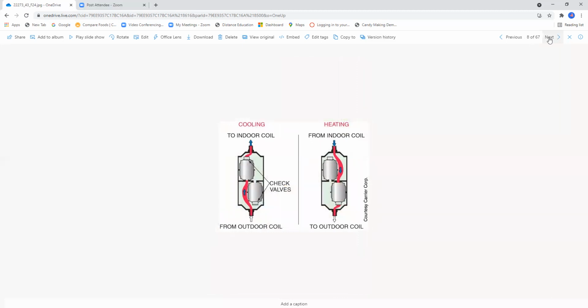Okay, here we have the check valves, basically on the cooling to the indoor coil. So basically, if we have refrigerant going from the outdoor coil, notice that it bypasses this one valve, goes directly through this check valve to the indoor coil. Now we go from the indoor coil, and notice we bypass this check valve, and then we go to the outdoor coil. One thing I've got to call your attention to, Carrier Corporation and some other manufacturers do incorporate these check valves in their coil designs, and you need to be aware that you could have problems with these. I've seen these check valves stick for whatever reason. Don't ask me why, but they do stick and they do cause problems.